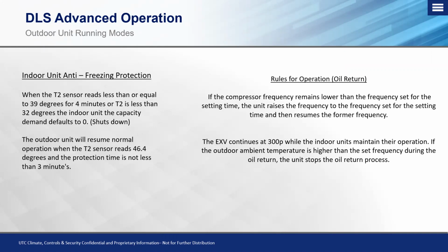So what we're going to do is we're going to take that compressor running frequency, and if it remains lower than the set frequency or the setting time, which is typically about half an hour, that unit is going to raise the frequency to the frequency set, or that we talked about that target frequency for the setting time, and then resumes the former frequency.